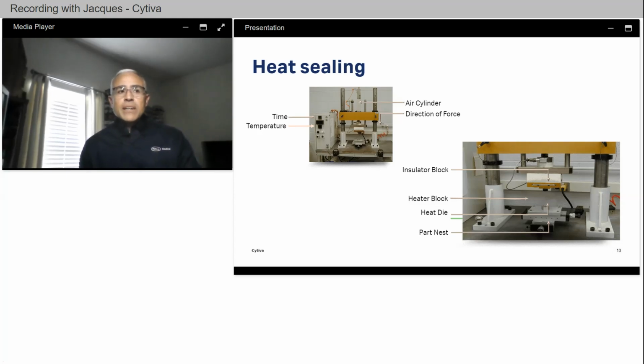Now, with heat sealing, it is possible to form two different types of bonds. The first type occurs if the filter and the housing material have similar thermal properties. In this type of seal, the material and the housing will melt together to form a molecular bond, which is very secure. The second type of bond occurs when the housing material melts at a lower temperature than the membrane. In this situation, the molten plastic from the housing penetrates the structure of the filter material, forming a mechanical bond. This type of bond relies on the strength of the plastic that interconnects with the physical structure of the membrane.